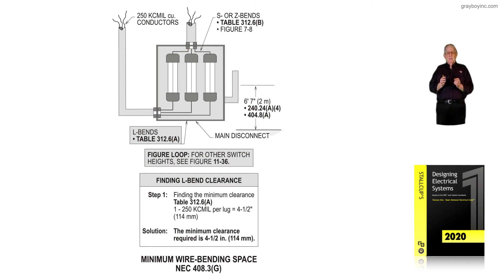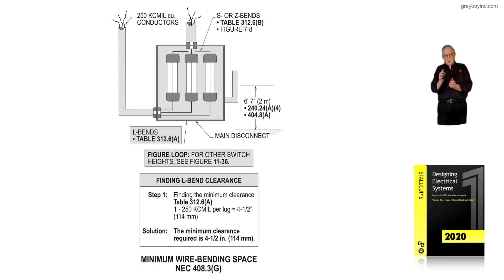Inspectors go to NEC 110.3A3 to see if the bending space is adequate. That section applies to all articles or sections of the code unless one of those articles or sections modifies it. So our figure 7-7, along with NEC 408.3G, deals with the minimum wire bending space — illustrated here when we're forming the conductors into an L-bend, as seen on the load side of that disconnect and those fuses.